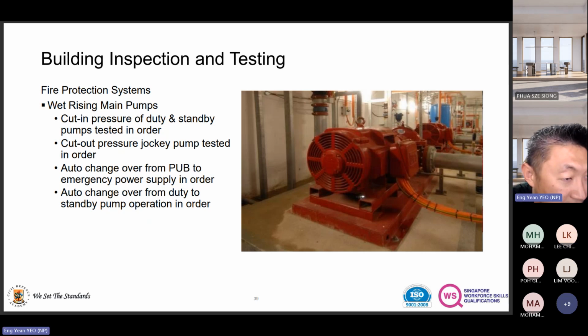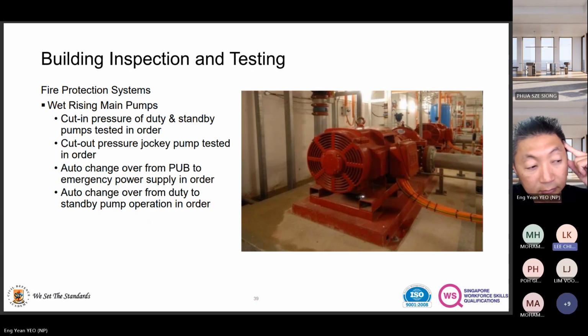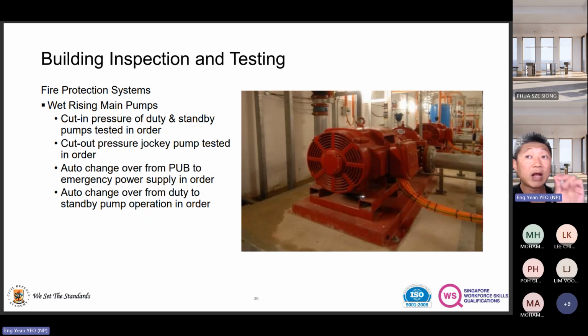Sorry, repeat your question. You are saying 180 degrees? Because your pipe itself is 180, right? Yep, 180 PSI throughout. But when you do the testing, after the testing you won't be at 180, right? So you have to restart again, and then the jockey pump will start until 180, it will cut off, then the whole system is on standby. That's normal practice, right? You ask me how to tune it, really I don't see that tuning part yet. But that can be adjusted by the fire protection vendors.